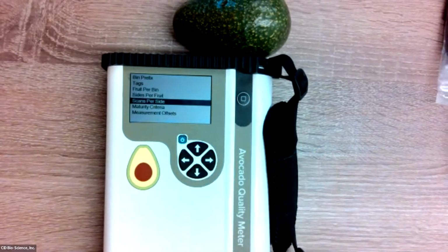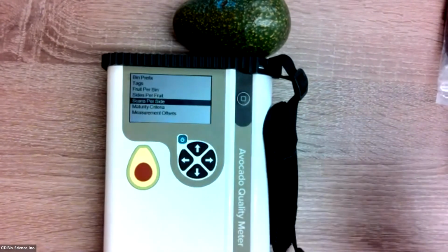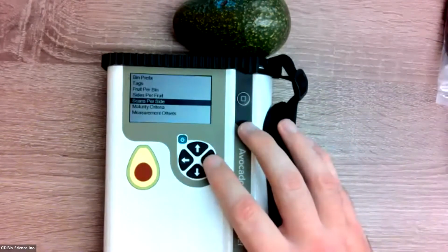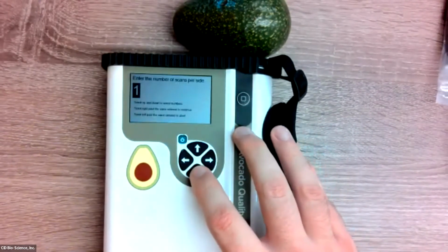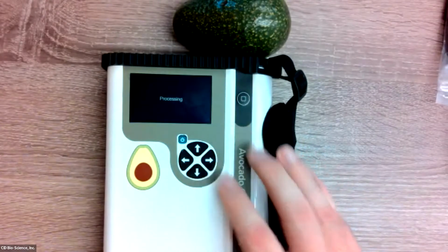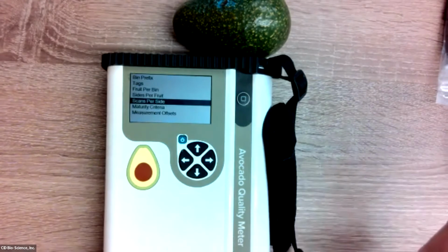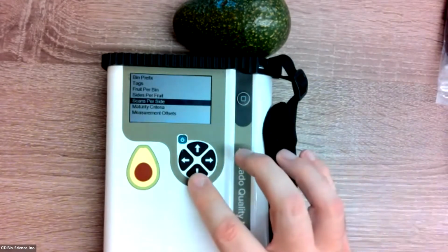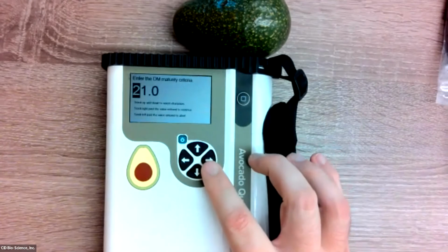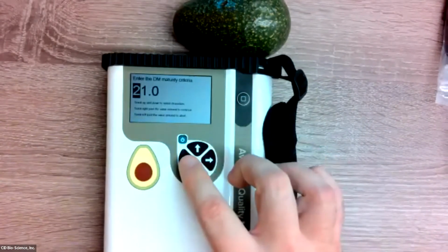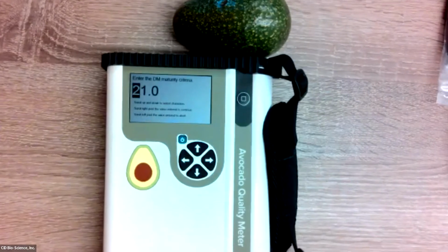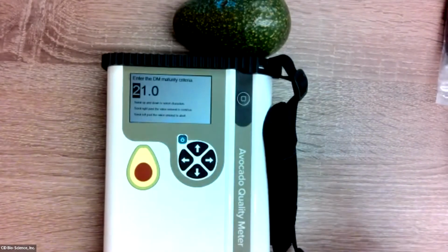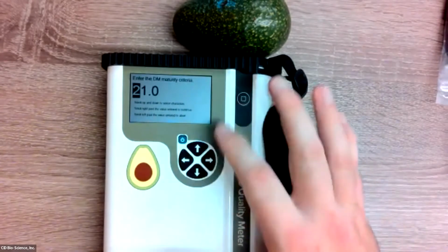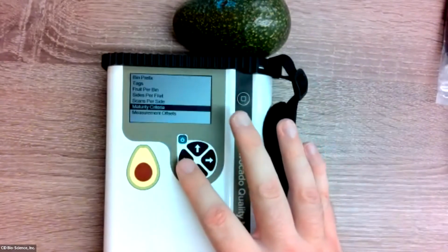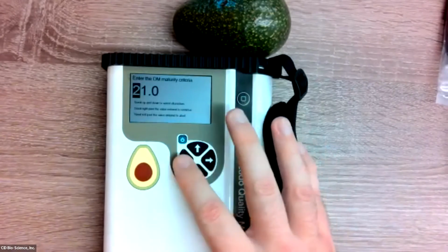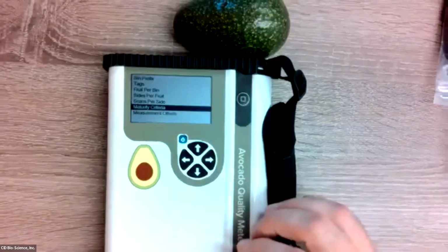The number of scans per side, that was the 3 automatic scans that were taken per side. If you don't want to do 3, if you only want to have that set to 1, you can set that down to 1, press the right arrow, save it. Now it's only going to take 1 scan per side. The maturity criteria, that's what I just talked about, that was set at 21. You can change this to whatever value you want. So if you want a statistic that says X% of my fruit that were scanned were greater than 18, you could change it to 18. You could change it to whatever value you want. The left arrow always cancels out of the menu, so you just click the left arrow to get back to the previous one.